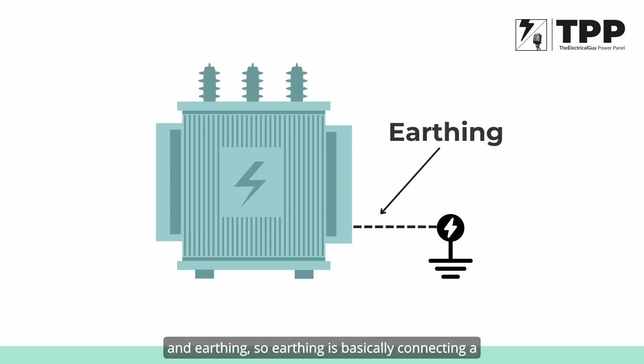Grounding is basically a system where you connect electrical equipment and/or conductors to the earth. We've all heard the term earthing—earthing and grounding can usually be used interchangeably depending on the country you're in. But to understand the subtle differences: earthing is connecting a non-current-carrying metallic part to the ground or earth. This helps ensure that whenever there is a short circuit or fault, metallic enclosures—switchgear, generator frames, circuit breakers, transformers, anything—safely dissipate the fault current to ground, while the person is not electrocuted.